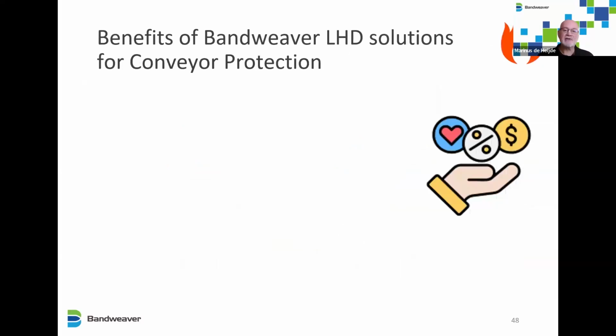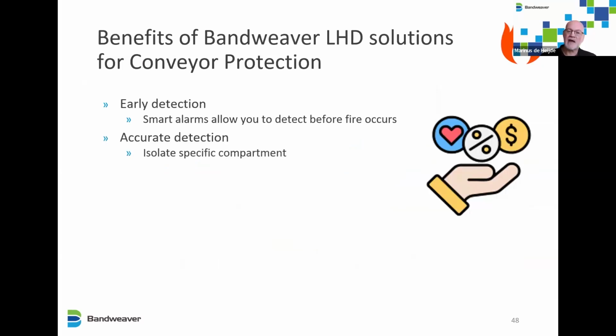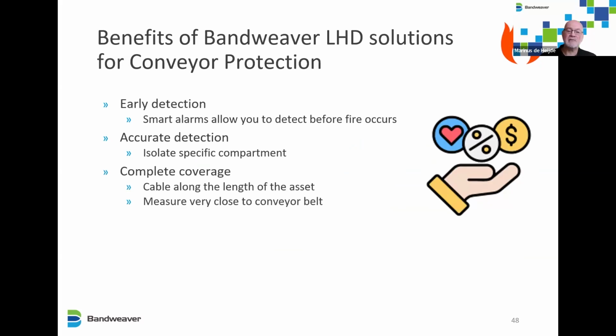So benefits of Bandweaver linear heat detection for conveyor protection. First of all, early detection. Smart alarms allow you to detect before the fire occurs. Very accurate detection. You can isolate specific compartments. As we've seen, we can detect within 1 meter. So we can then shut down a belt, for example, and send a maintenance team.